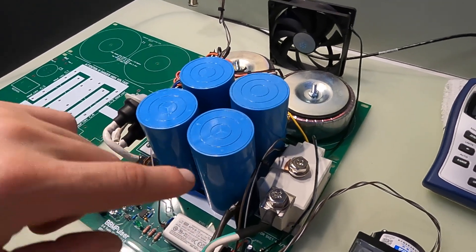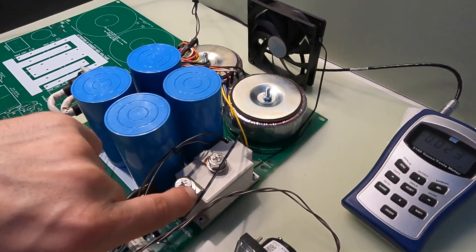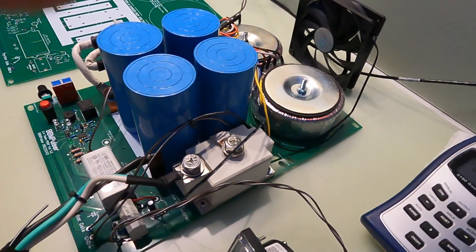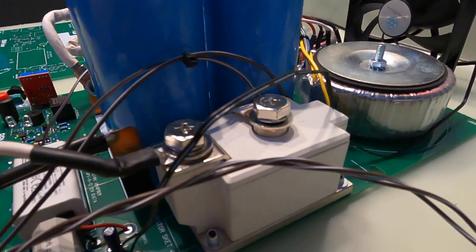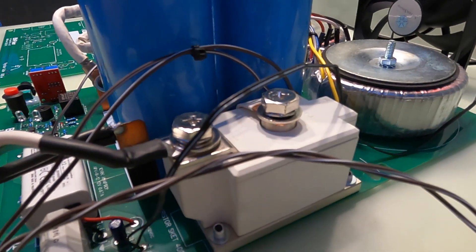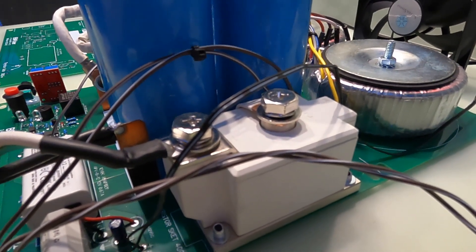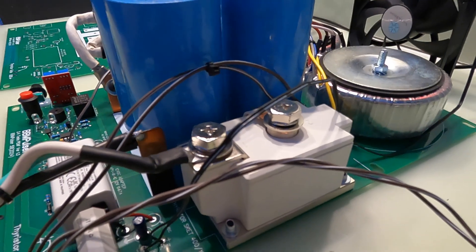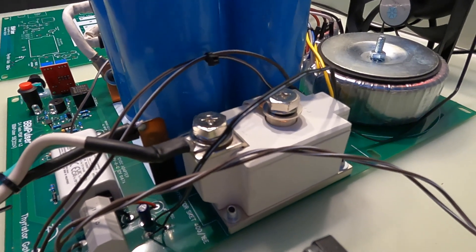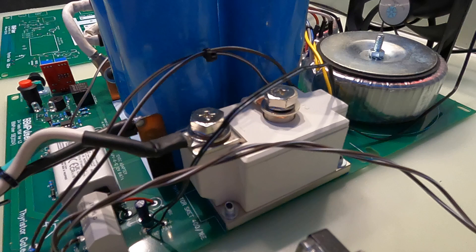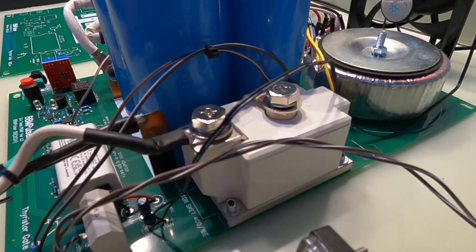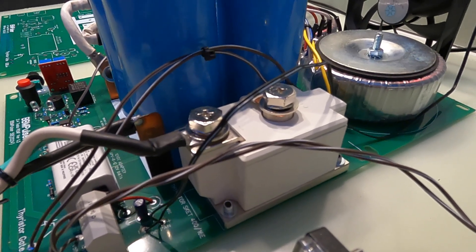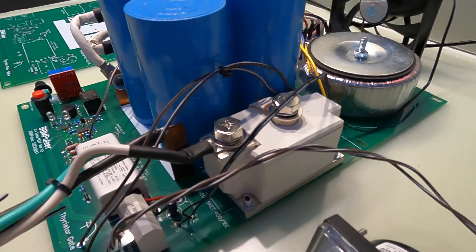On this side here I have a thyristor. This is Semikron 400 amps, 1.6 kilovolt thyristor. The reason why I'm using this large of a thyristor, actually like four times larger than you should use, is because...